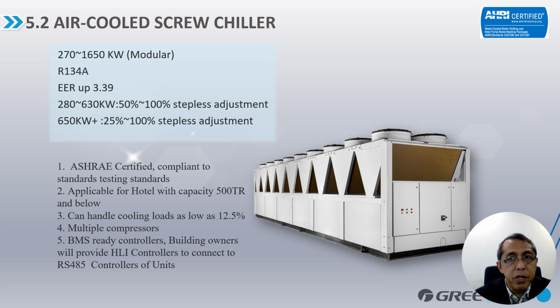For the air-cooled screw chiller, it's an AHRI certified chiller. It uses R134A refrigerant and the EER is up to 3.39. This unit, we installed this in Bicol International Airport, I believe. We helped that group to complete the chiller design as well as the installation.